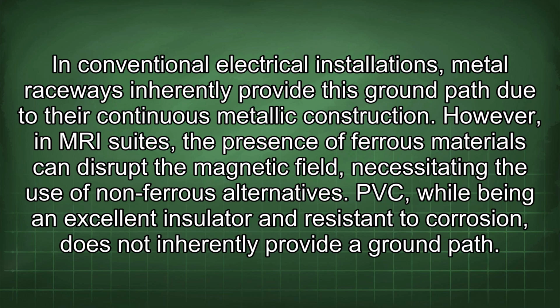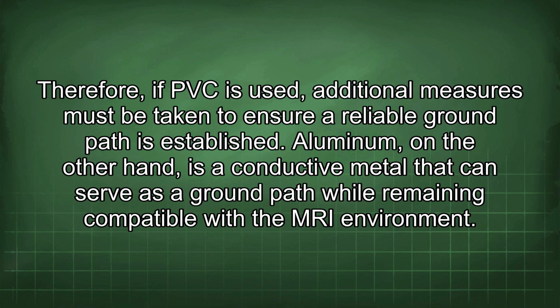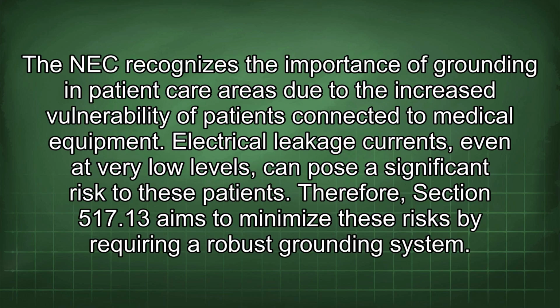PVC, while being an excellent insulator and resistant to corrosion, does not inherently provide a ground path. Therefore, if PVC is used, additional measures must be taken to ensure a reliable ground path is established. Aluminum, on the other hand, is a conductive metal that can serve as a ground path while remaining compatible with the MRI environment. The NEC recognizes the importance of grounding in patient care areas due to the increased vulnerability of patients connected to medical equipment. Electrical leakage currents, even at very low levels, can pose a significant risk to these patients.